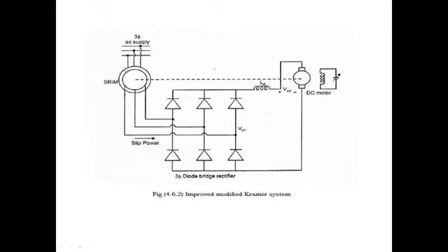Since in the slip power recovery scheme the slip power is fed back to the source, unlike rotor resistance control where it is dissipated in the resistor, drive input power is the difference between motor input and power feedback. Reactive input power is the sum of motor and inverter reactive powers. Therefore, the drive has a poor power factor throughout the range of its operation, where alpha is the inverter firing angle and N and M are the turns ratios respectively to the stator.